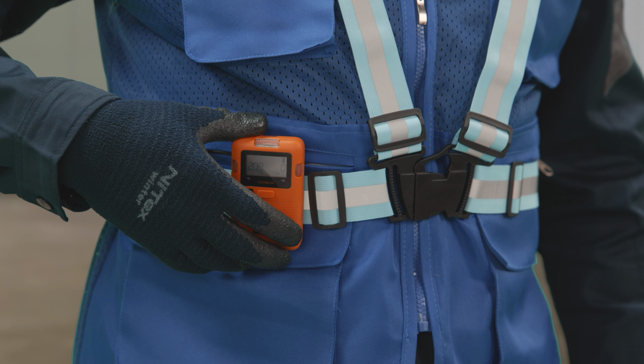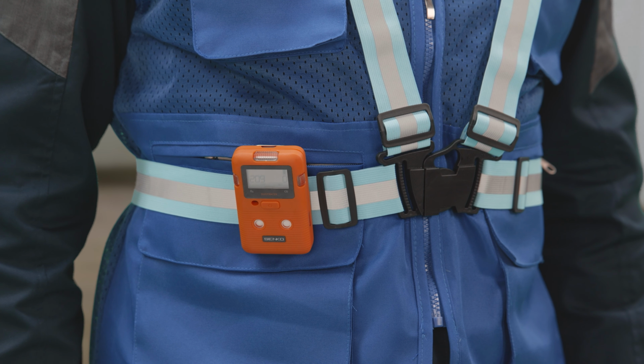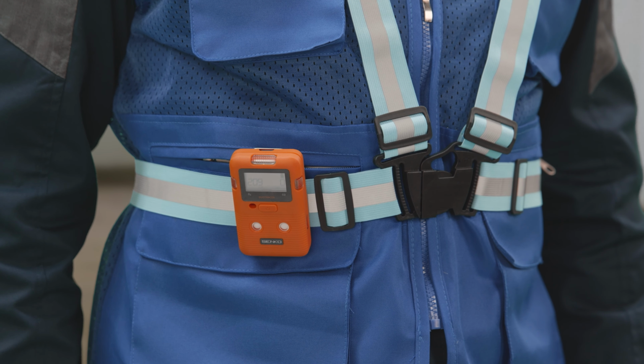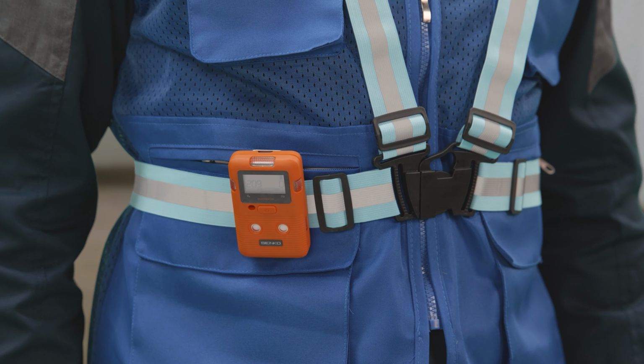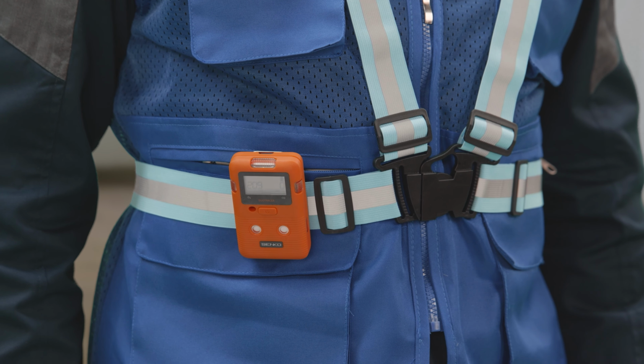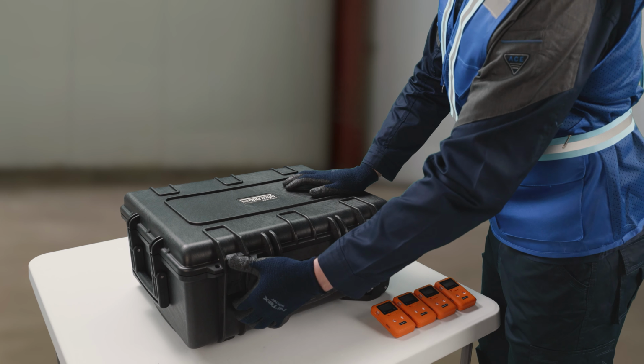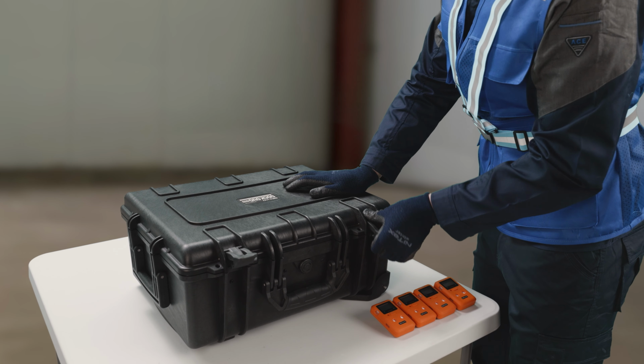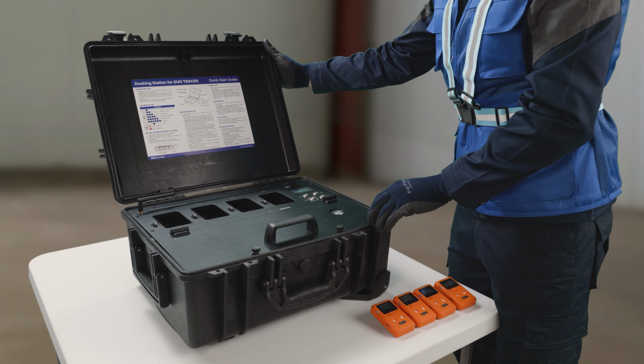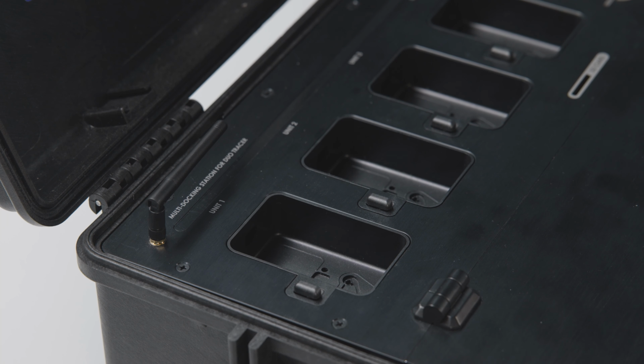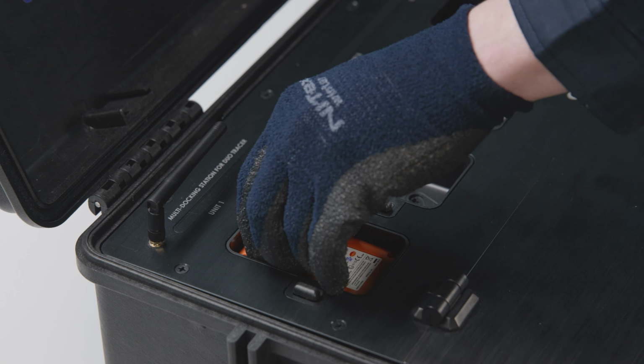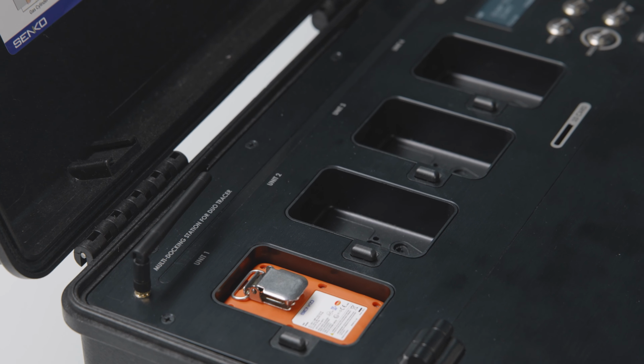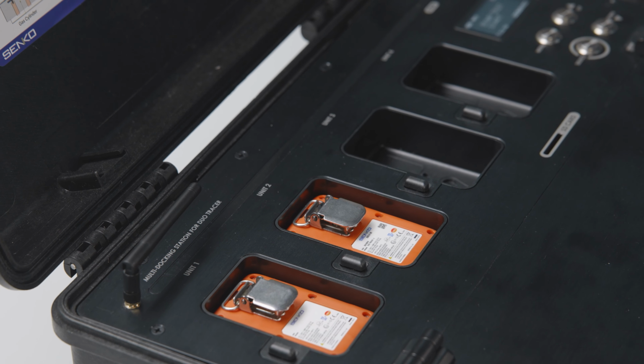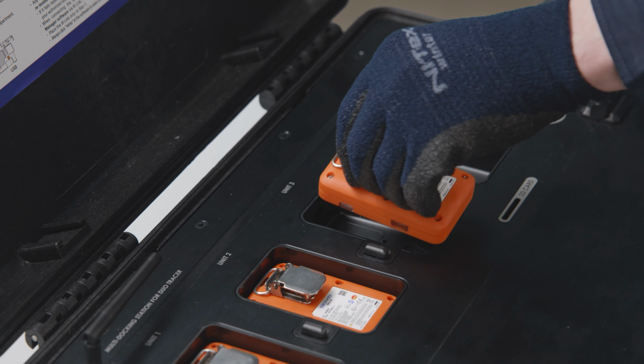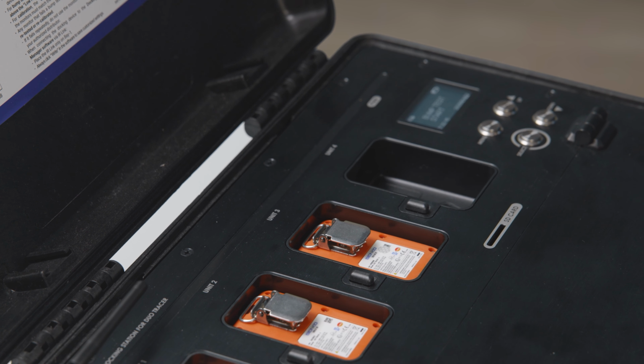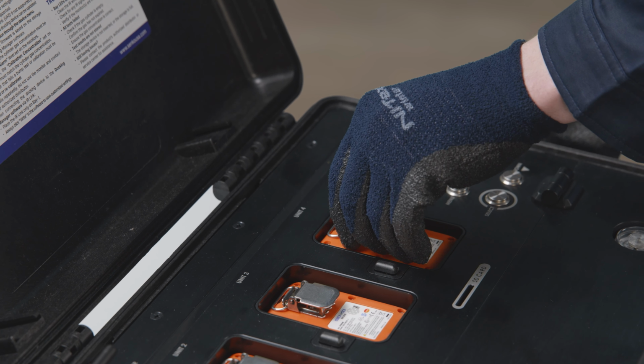Duo Tracer also works with a dedicated docking station, Duo Dock, to make bump testing and calibration more systematic and efficient. Once the device is placed on the Duo Dock, the bump test or calibration starts automatically based on preset conditions. Recognition of the device, injecting gas, showing the result, will proceed in order. This means operators can carry out inspections using a standardized procedure without repeating manual tasks.